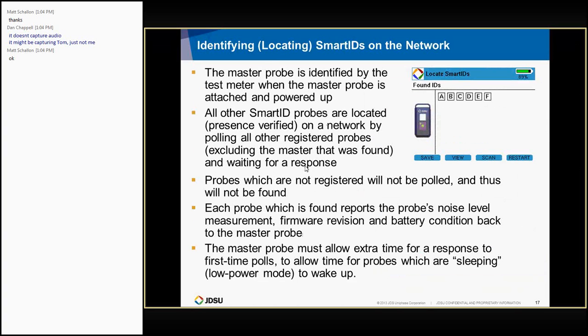So is the registering done once per test set, really, or at the beginning of every test? No, you just register your probes. So when you get a set of probes, the technician would register those on his meter, and then the registration stays there until he has to replace a probe or add some more probes, so he doesn't have to disturb the registration. And he does that by connecting the probes individually through the USB. He can manually enter the serial number also, but the smart way is just to attach it and let it read the serial number and put it up on the screen.